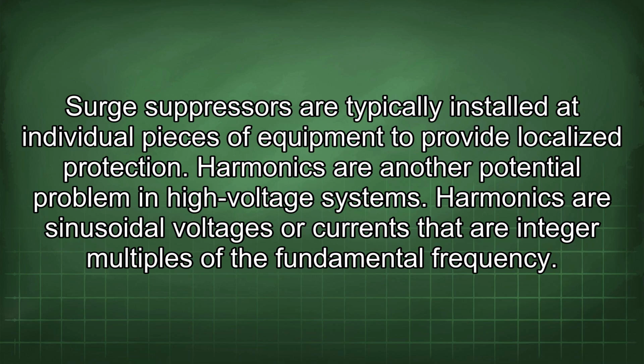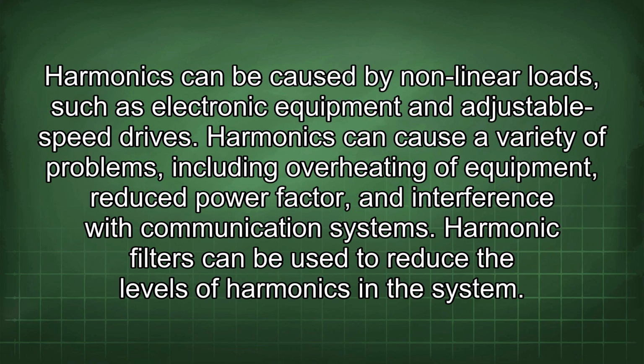Harmonics are another potential problem in high voltage systems. Harmonics are sinusoidal voltages or currents that are integer multiples of the fundamental frequency. Harmonics can be caused by nonlinear loads such as electronic equipment and adjustable speed drives. Harmonics can cause a variety of problems, including overheating of equipment, reduced power factor, and interference with communication systems.